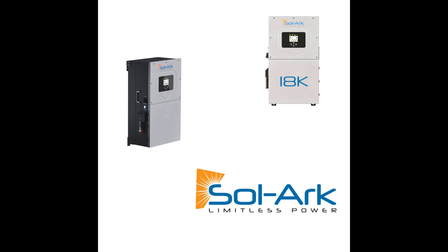Now, something really cool we did with the Sol-Ark 18K: we actually made it true to its name, so you will get 18 kilowatts of discharge from the battery. And there's no other product on the market today that gets a true 18 kilowatts from battery as an advertised nameplate rating of the inverter. So it is the strongest inverter on the market today, with 18 kilowatts continuous discharge from battery or PV. That looks like 375 amps on the DC side at 48 volts.